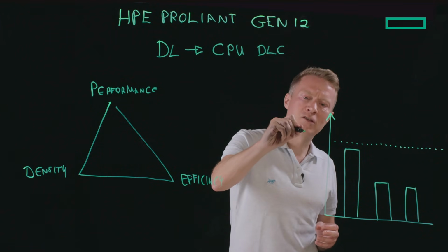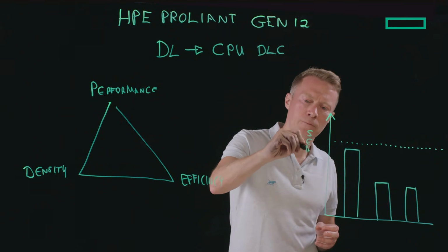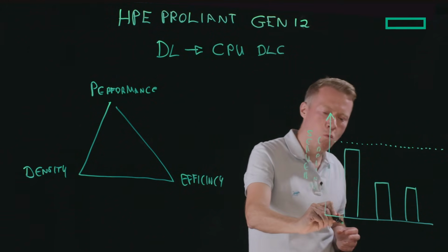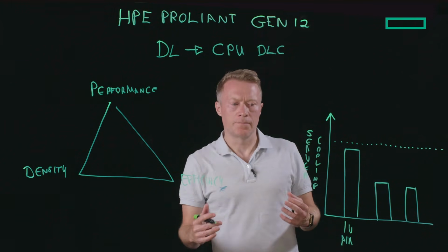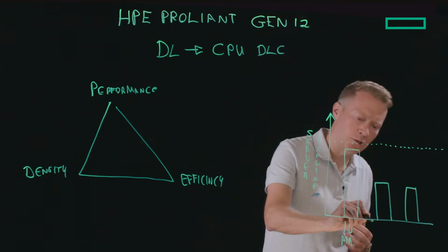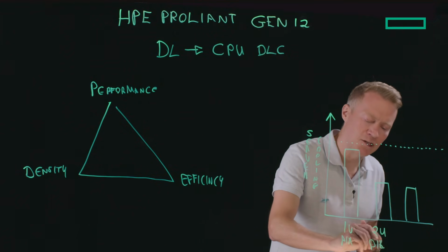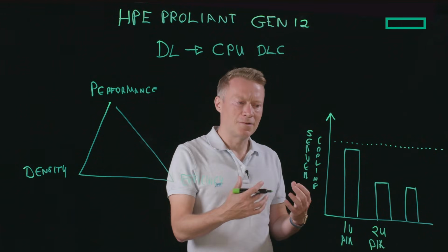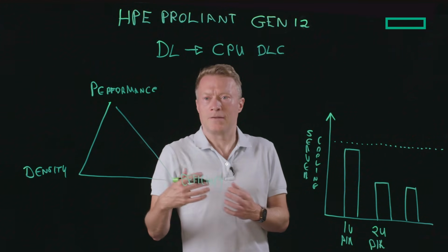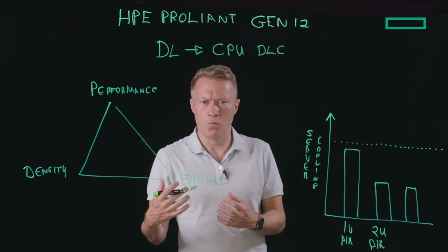If we take the server cooling, so this is the power to cool a server, not to run it, then relatively, this one on the left is a 1U air. So a DL360, for instance. You can actually make some really good savings, and we're starting to see this more and more often, by going to a 2U air server. So this is a mitigation in effect. This can save you significant cooling power, particularly because the fans are more efficient. And then, as I discussed earlier, if you go to a single processor, you can save even more power.